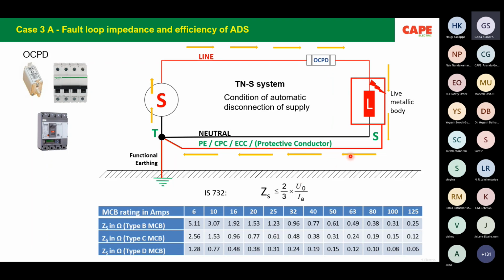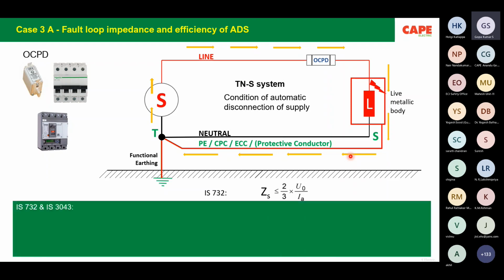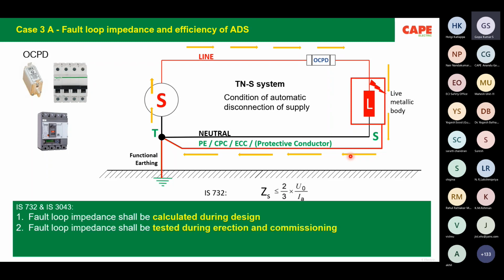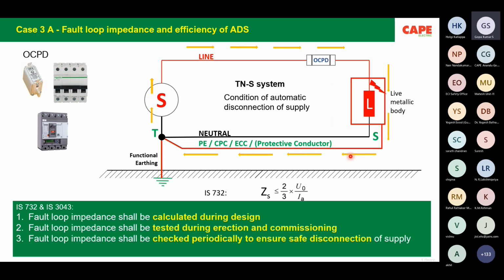Now imagine, instead of a class 2 copper wire, if you use a class 5 copper wire, impedance is higher. Your MCBs won't trip. Unfortunately, you are violating the requirements of the standard. Fault loop impedance shall be calculated during design, tested during erection and commissioning, and checked periodically to ensure safe disconnection of supply. And the first job of an electrical safety auditor is to measure and cross-check this disconnection time. As I said, unfortunately, nowhere is this carried out.